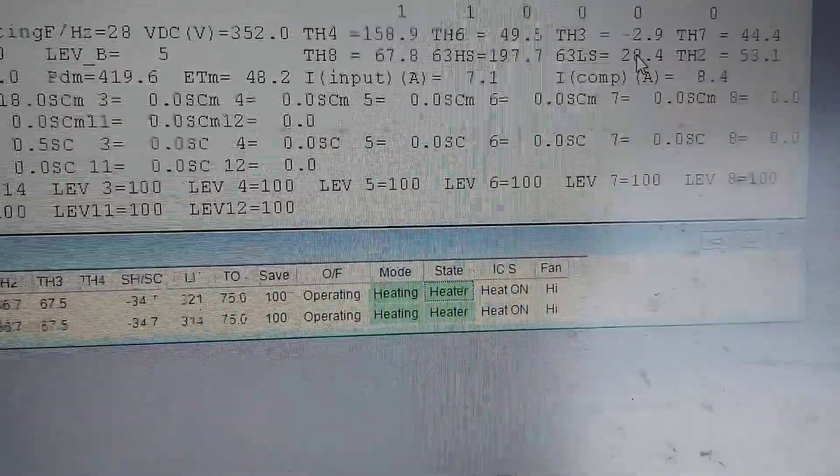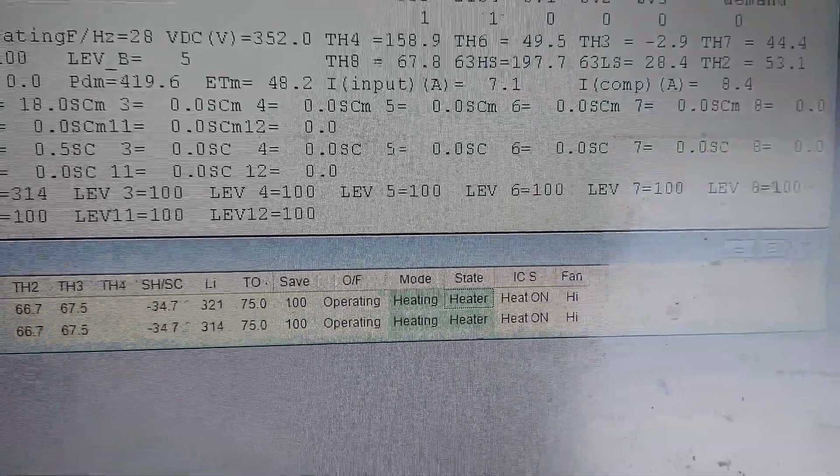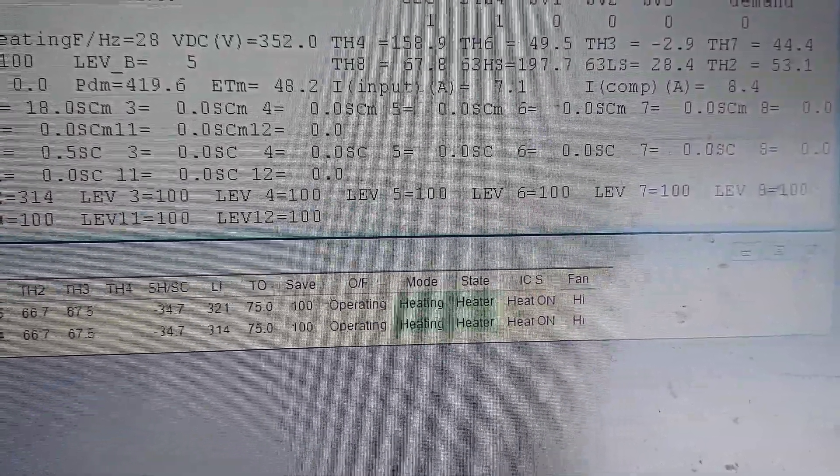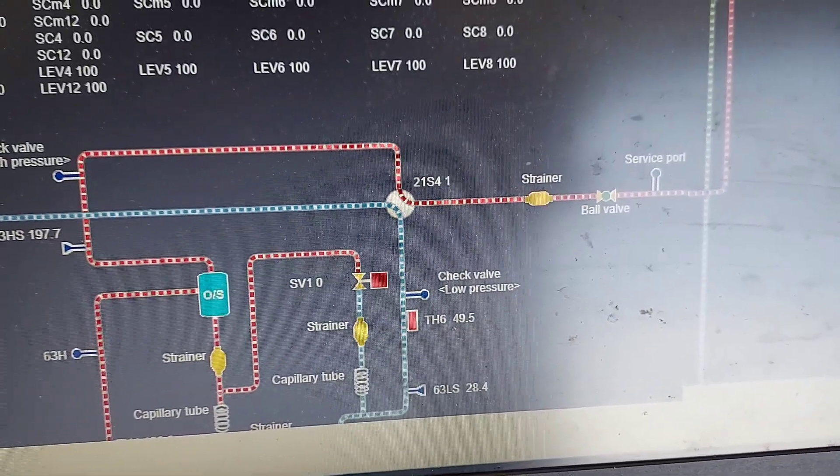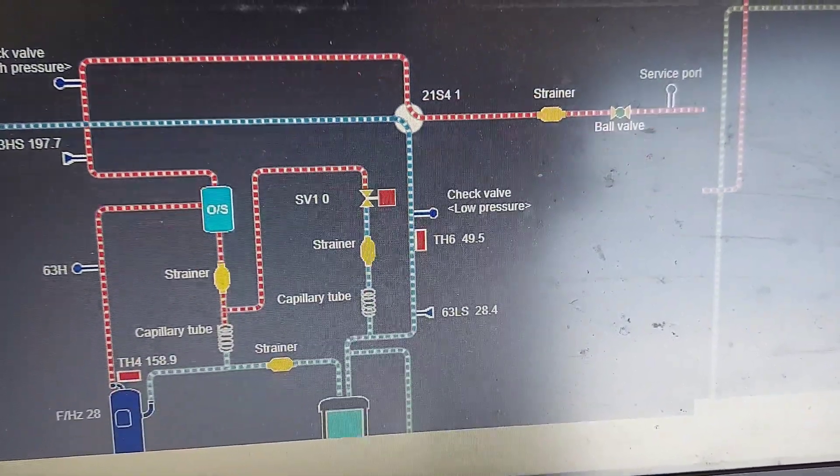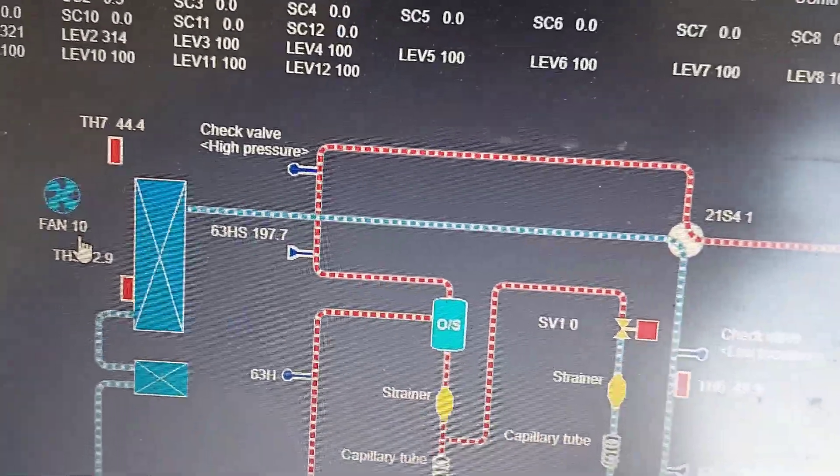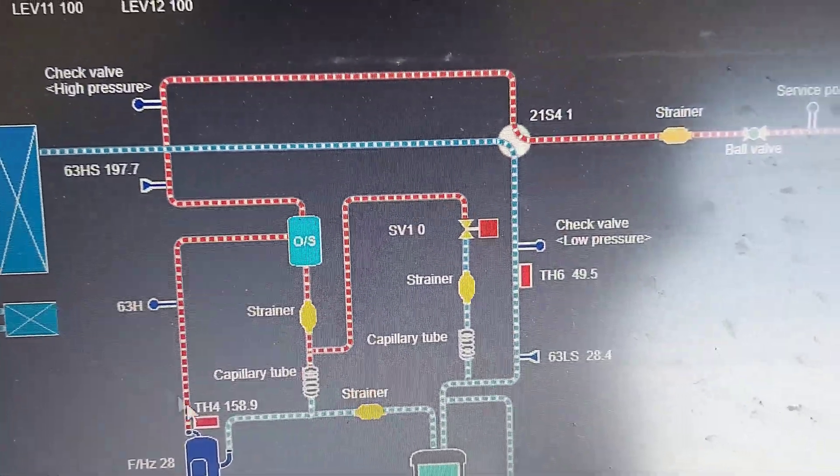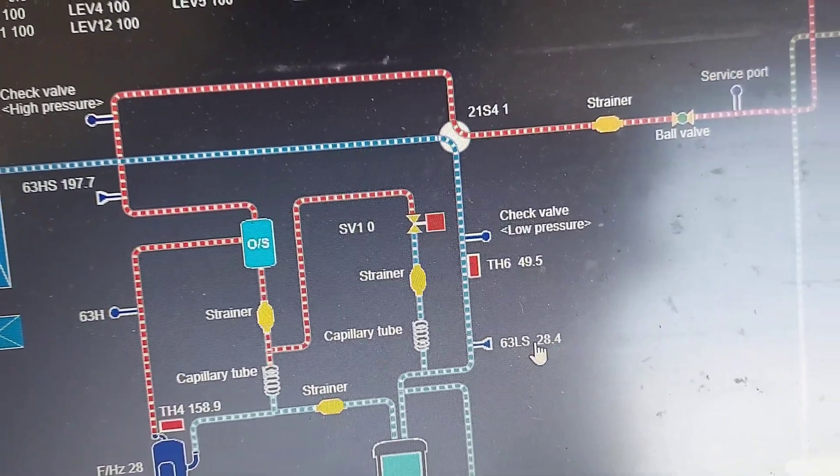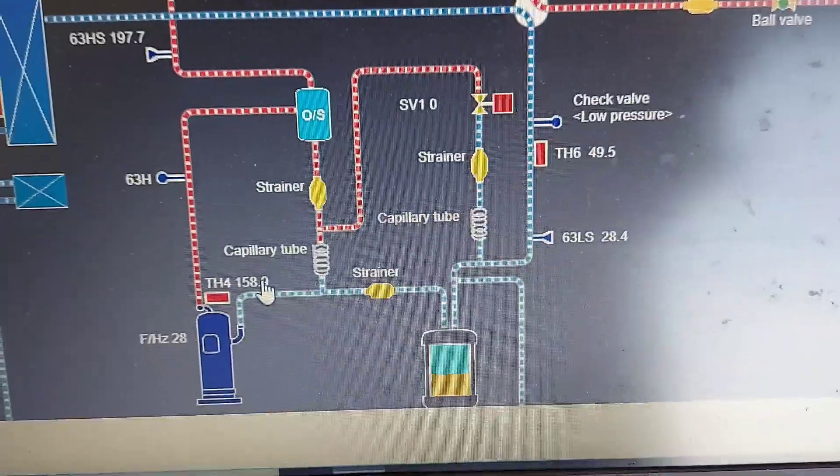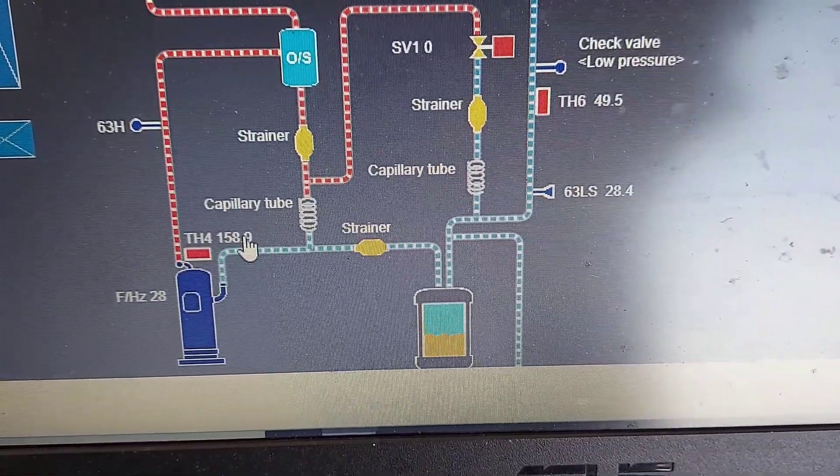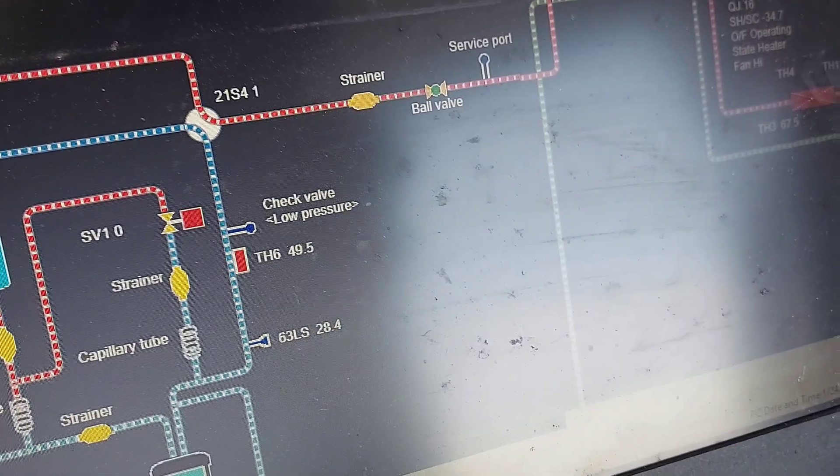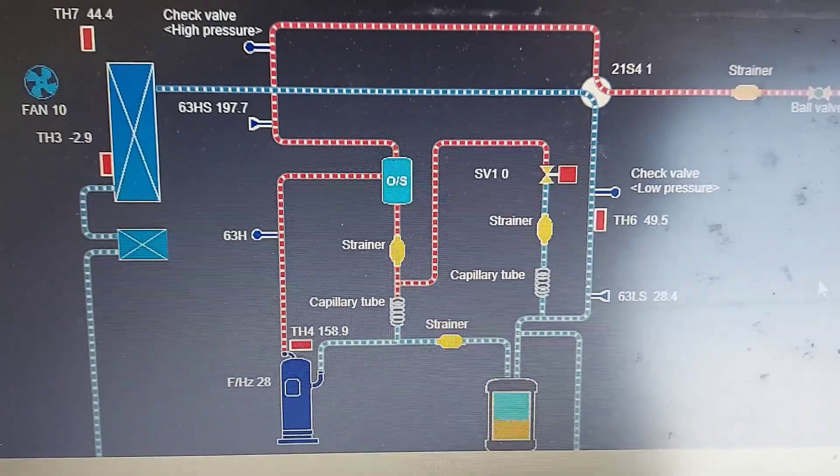Low side is 28, high side is 197. Go back to our diagram. Compressor, what we're doing, the fan is only running at 10, I think that's full speed for this unit. But compressor's at 28, 28 low side, we're in full heat, we're at 158 on a discharge, which is what gives that error, but we're still at 67, we ain't moving on the inside. So yeah, that's the diagnostic guys.